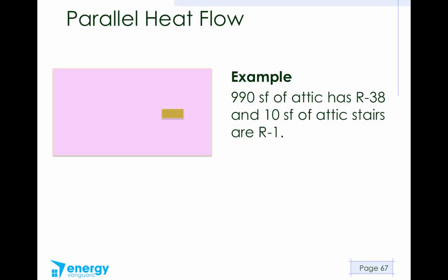Let's look at an example here. This is a simple parallel heat flow problem. Let's say we've got a ceiling, and it's 1,000 square feet total. 990 square feet of it has R38 insulation, but we've got 10 square feet of attic stairs that's uninsulated, and we're going to call that R1. If you want to try this problem yourself, hit the pause button and see if you can calculate the average U value and the average R value for this parallel heat flow problem, and then come back and see if you got it right.